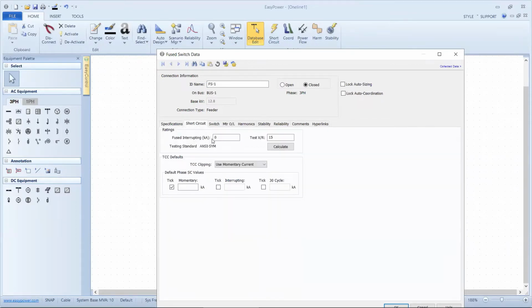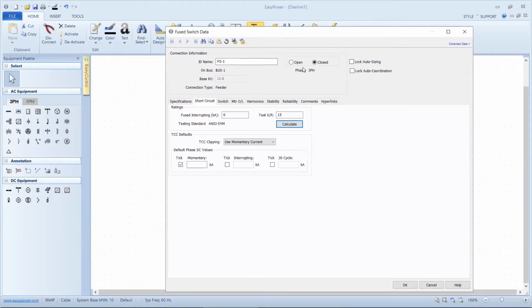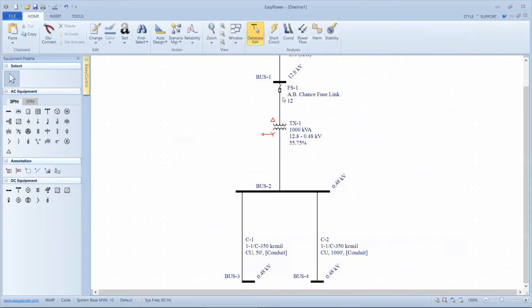So when I go to short circuit, I want to connect to the device library by hitting calculate. The fact that this number comes back with 15, the tool says I've found the device data sheet for this part number. The manufacturer tested to an ANSI standard, and the X over R environment at the test fixture was 15. The reason that's important is EasyPower will calculate the X over R at every bus, and wherever there's a protective device, it will compensate for the difference between the manufacturer's test environment and our installed part.